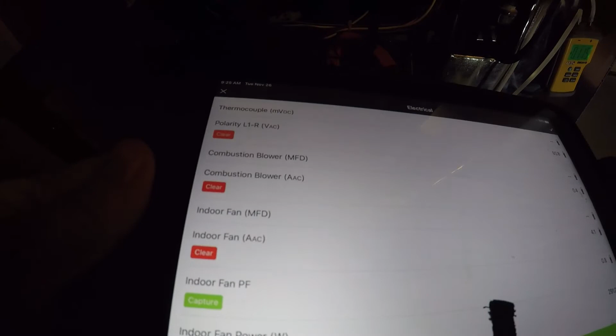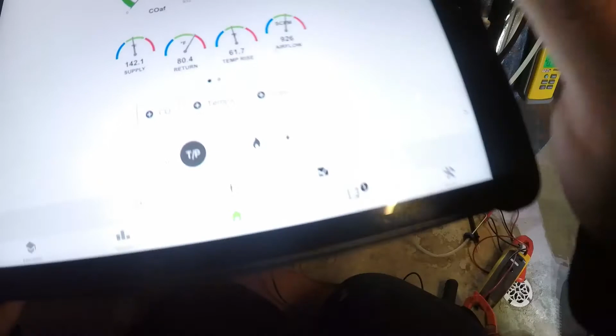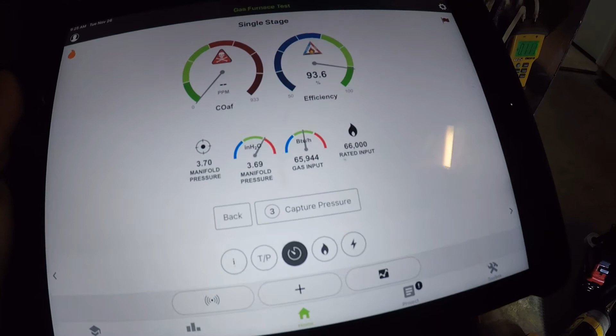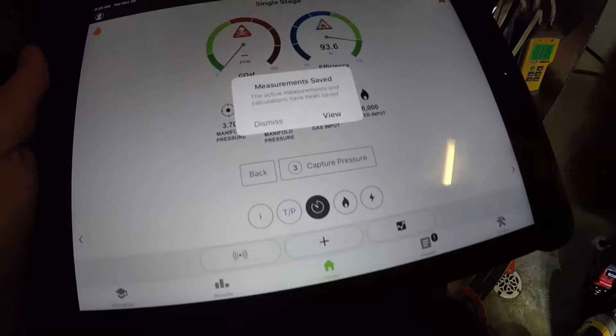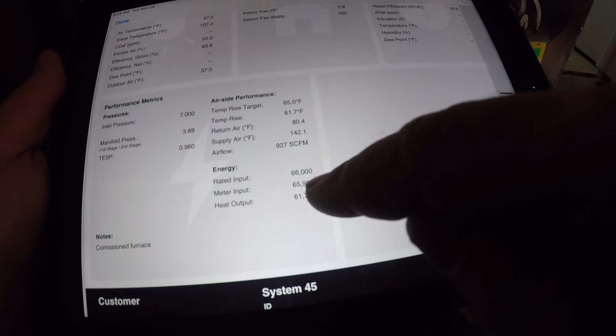If I clamp my main line, there we are, 290 watts, so I'll capture that. My power factor is 0.8. We'll submit that. And we got all our numbers. Basically at this point, I shut everything off, I clean it, show it to the customer, and I provide them a commissioning report, which will look something like this. Once I get outside, I'll have my internet, but it gives me all my metrics, fully commissioned, you know, rated input 66,000, meter input 65, looking really good, guys.